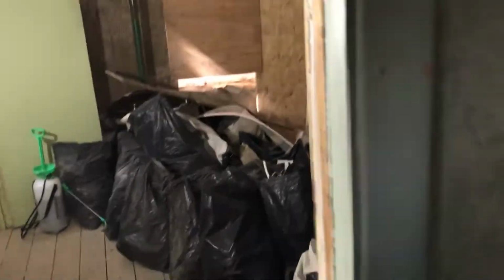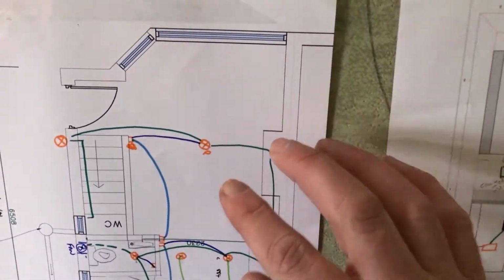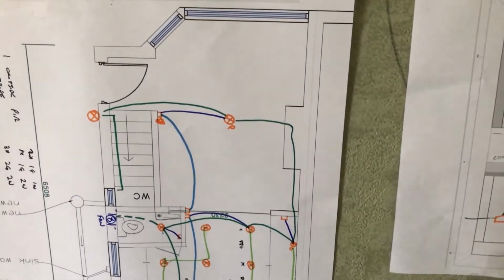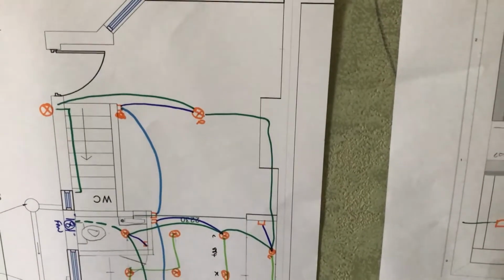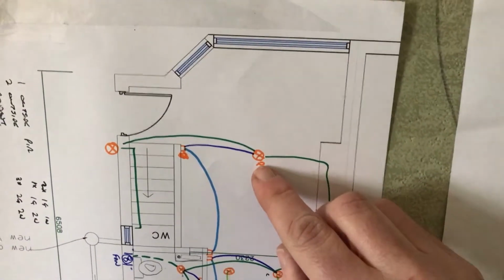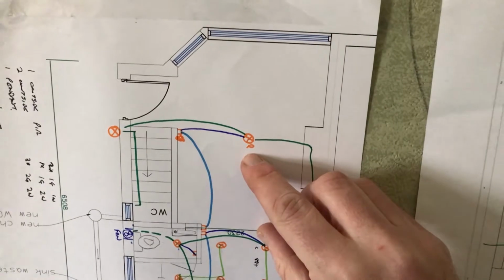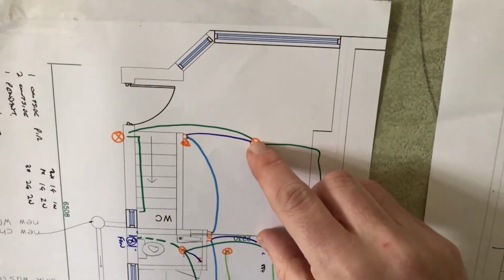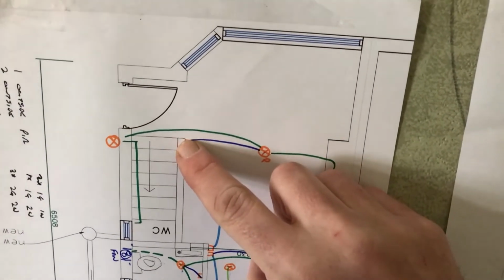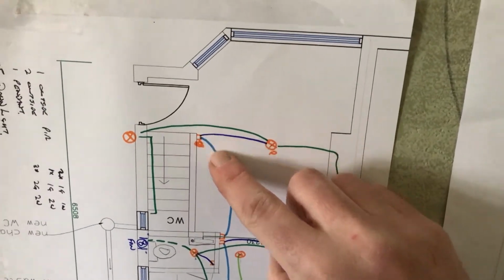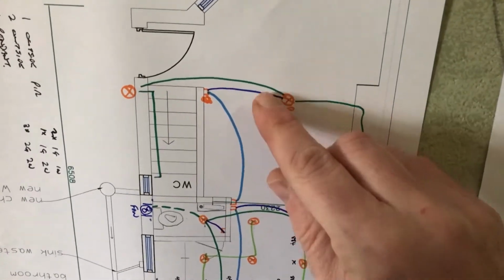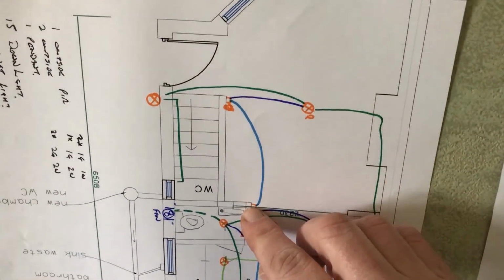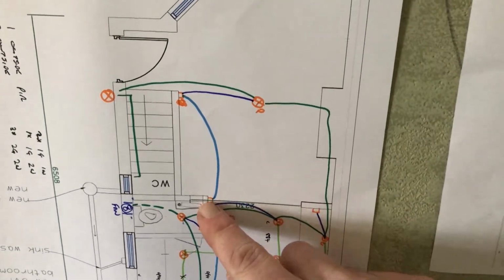So the living room, which currently is a bit of a skip. You don't need a whole lot of light in a living space, and a lot of the light would be accent lights, as in lamps beside your sofa, rather than ceiling lights. So the only ceiling light I'm going to put in is this pendant in the middle of the room. So the pendant goes there. I obviously need a switch by the door as I come in the room, and another switch over here as I leave the room, or vice versa. So it's a 2-core down to this one and a 3-core to this one, so I can get two-way switching.